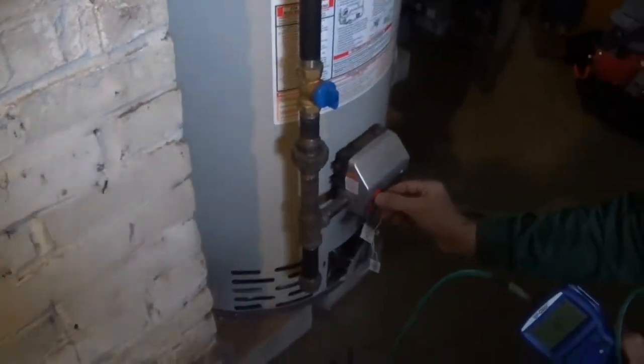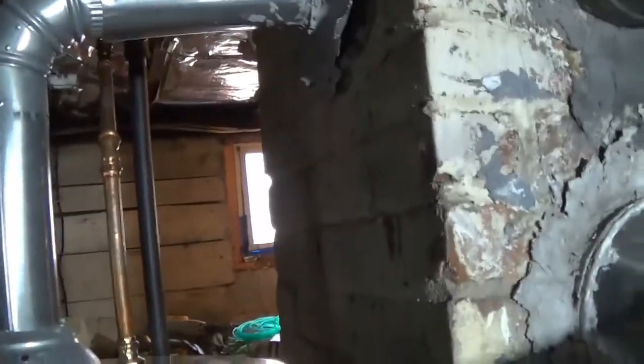All right, so now we've got the furnace, the boiler, the main heating system running, and now we want to see what its influence is on the water heater again. So we turn this back on. Sometimes it will help, sometimes it will hurt. All right, so now it's on. I heard it come back to life. I'm going to get my smoke pencil out again.